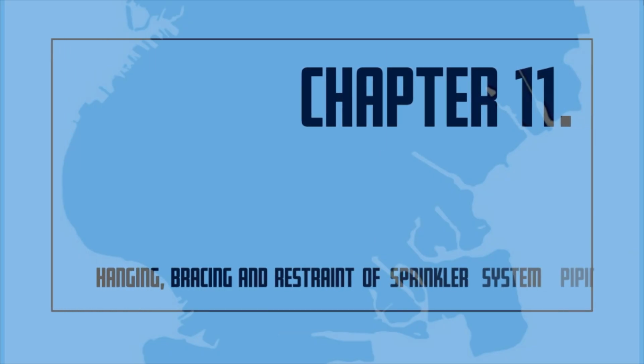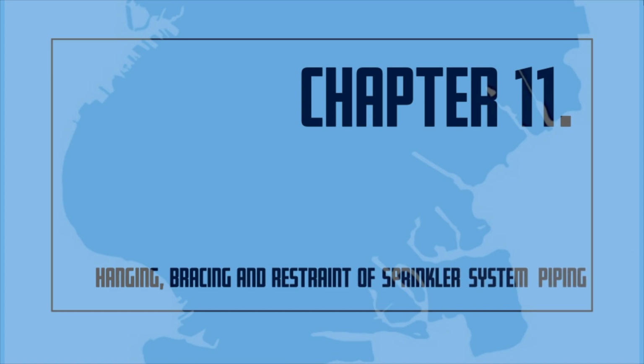Chapter 11. Hanging, bracing, and restraint of sprinkler system piping. The structural support of the sprinkler system plays an integral part of system reliability. Missing or defective pipe hangers can cause the entire system to fail from pipe rupturing or leaking. Great care and experience must be applied when evaluating the adequacy of the structural support of the system.